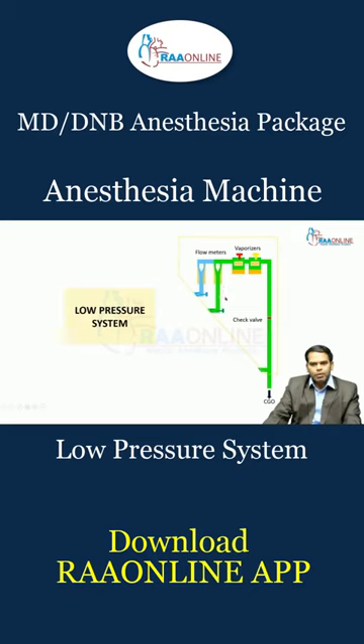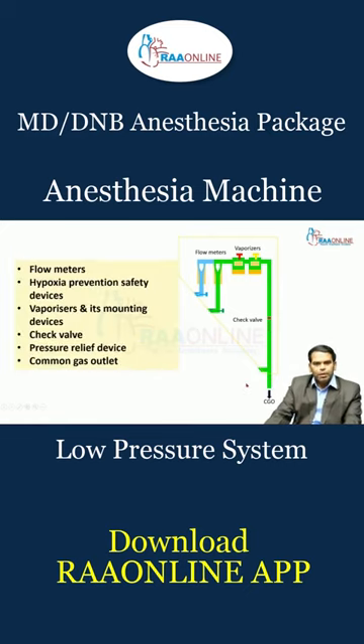This pressure range is based on the flow from the flow control valves and the presence of back pressure devices like check valves and back pressure from the machine. The components included in this system are: flow meters, hypoxia prevention safety devices, vaporizers and their mounting devices, the check valve, the pressure relief device, and the common gas outlet.